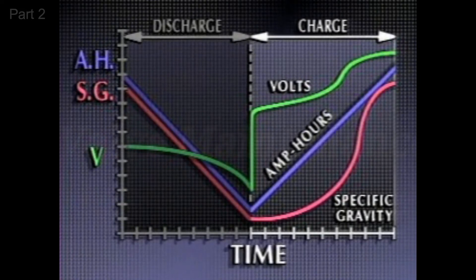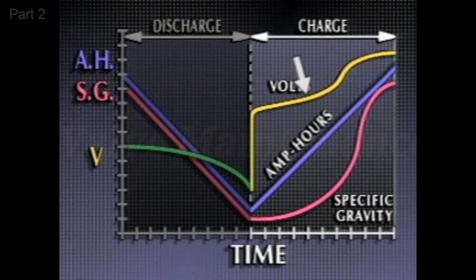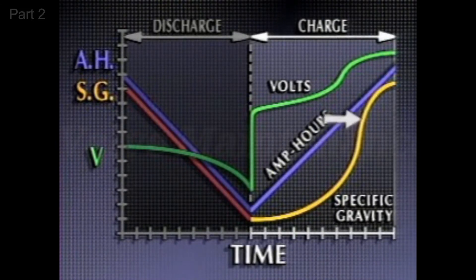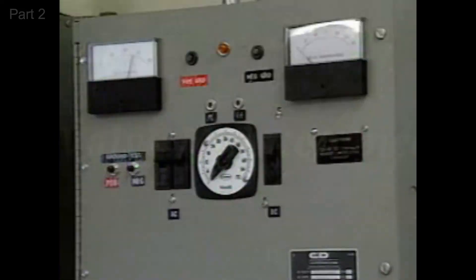However, when the cell is recharging, cell voltage and specific gravity change at irregular rates. Cell voltage jumps instantly and then gradually increases until it matches the output voltage of the battery charger. Cell specific gravity increases gradually as sulfuric acid is driven off the cell plates and mixed with the electrolyte. It may take weeks or even months for the sulfuric acid to thoroughly mix with the electrolyte and for the specific gravity to return to its normal value. Because cell voltage and specific gravity change at irregular rates when the cell is recharging, they are not reliable indicators of cell ampere hour capacity during recharging.